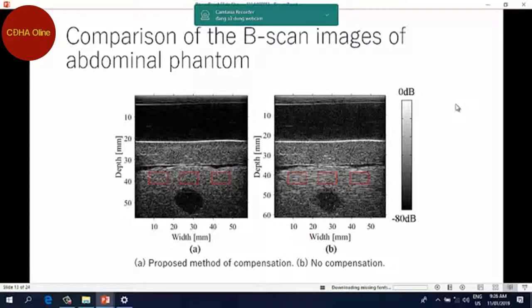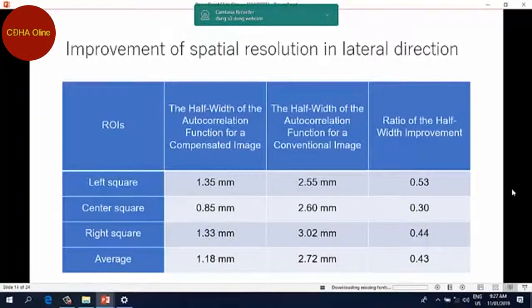If you take a look at this red area, you can see the spatial resolution is better than this. So in this example, it is important to obtain the sound velocity distribution beforehand when imaging by ultrasound. And this shows the results of the spatial resolution in the 3 red square areas.